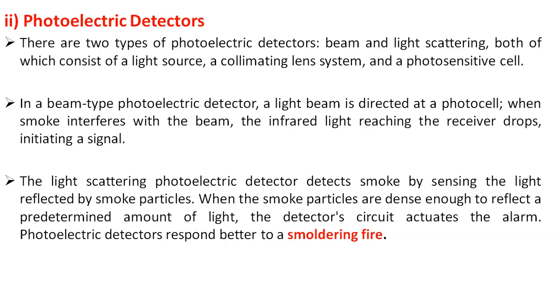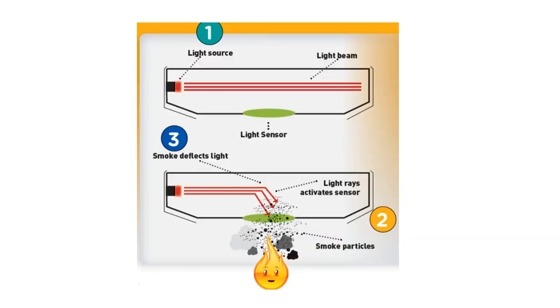In the light scattering photoelectric type detector, the sensor and the emitter are placed perpendicular to each other. Under normal conditions, the sensor receives no light. Whenever smoke enters the detector, the light is scattered and reaches the sensor, giving an alarm indication. This scatter type photoelectric detector works such that when smoke enters, scattered light passes to the sensor, which triggers an alarm condition.